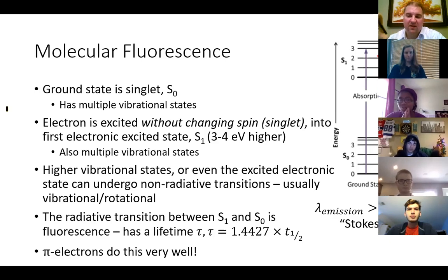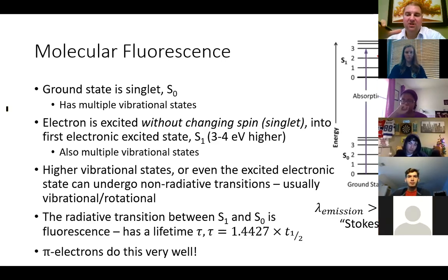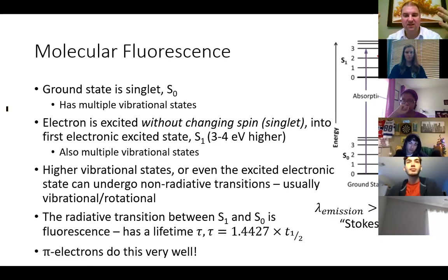The key with all of this is that we're using these electronic states of these molecules to collect all of the energy that's deposited in the liquid solution and turn all that into light. So whenever an alpha particle or a beta particle gets emitted, it's going to deposit energy in the solution. That energy causes the liquid to get excited. The liquid transfers its excitation energy to our scintillating molecules. Our scintillating molecules get excited and then fluoresce.